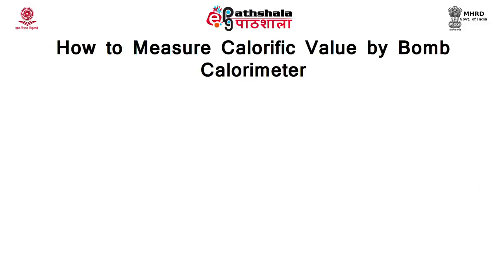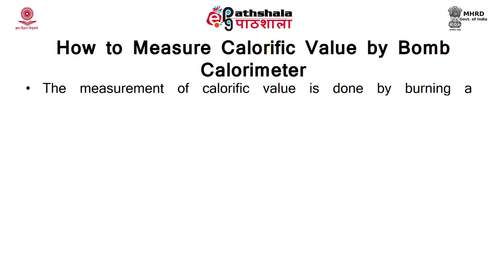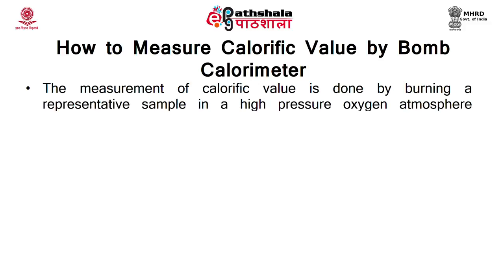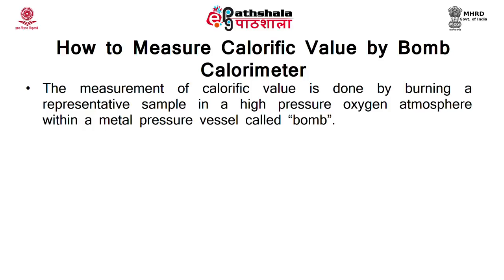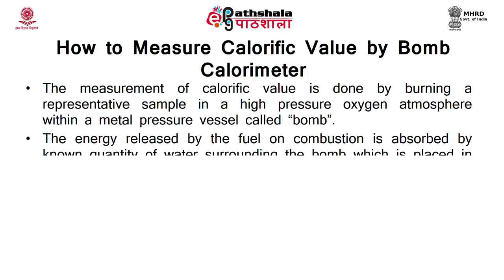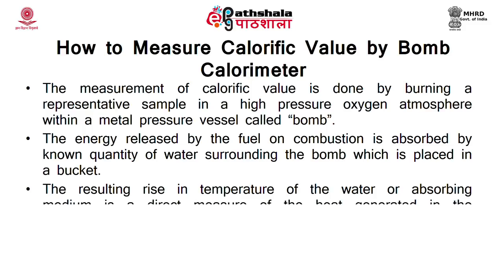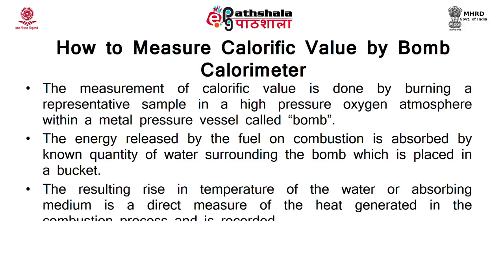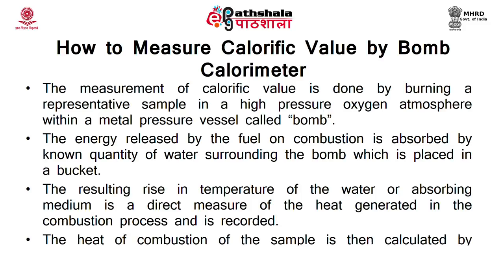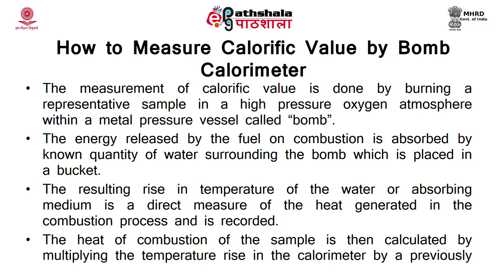Let us see how to measure calorific value using the bomb calorimeter. The measurement is done by burning a representative sample in a high-pressure oxygen atmosphere within the metal pressure vessel called the bomb. The energy released by the fuel on combustion is absorbed by a known quantity of water surrounding the bomb in a bucket. The resulting rise in temperature of the water is a direct measure of heat generated in the combustion process. The heat of combustion is then calculated by multiplying the temperature rise by a previously determined energy equivalent.